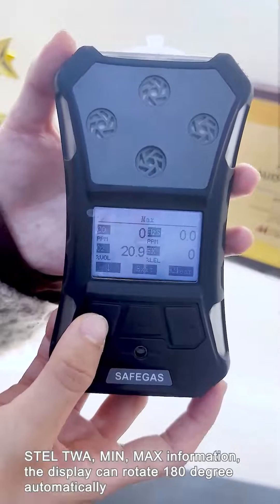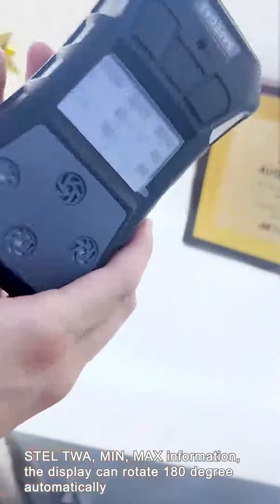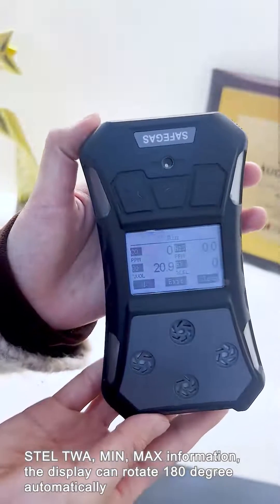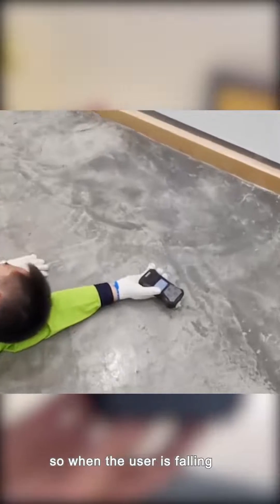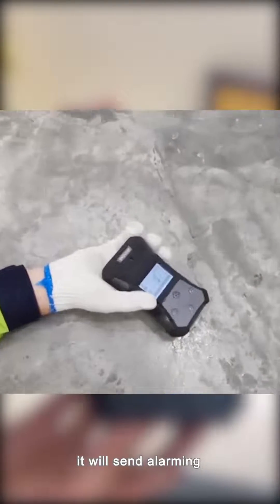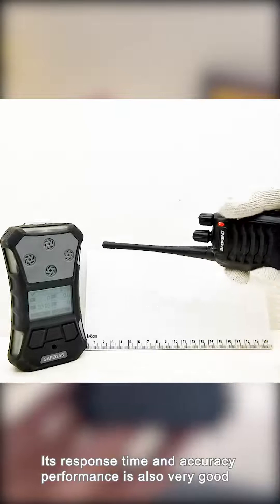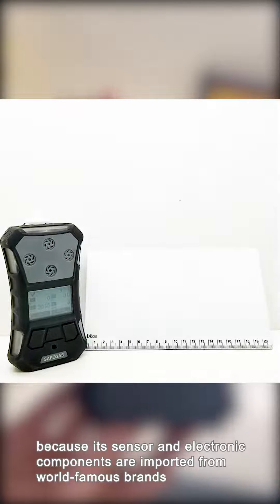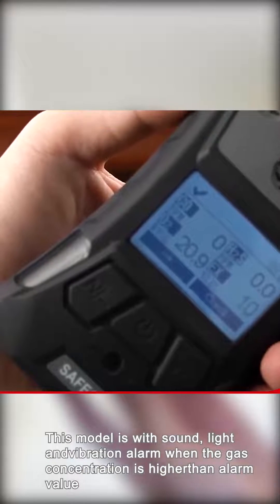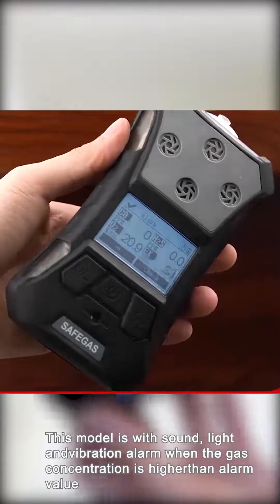STEL, TWA, MIN, and MAX information is displayed. The display can rotate 180 degrees automatically. It is equipped with a standard man-down function, so when the user is falling, it will sound an alarm. Its response time and accuracy performance is also very good because its sensor and electronic components are imported from world-famous brands. This model features sound, light, and vibration alarms when the gas concentration is higher than the alarm value.